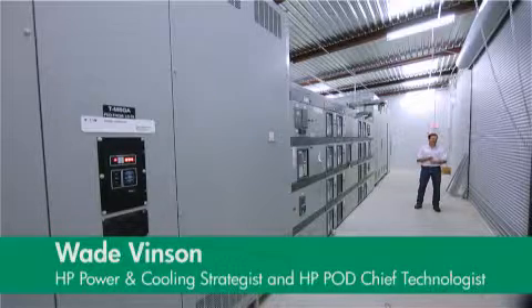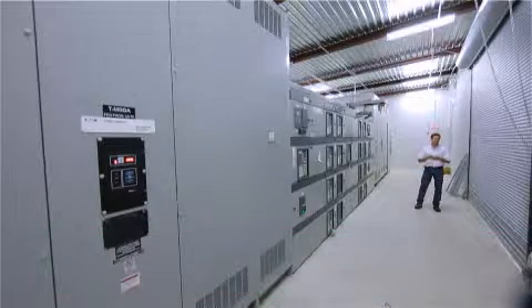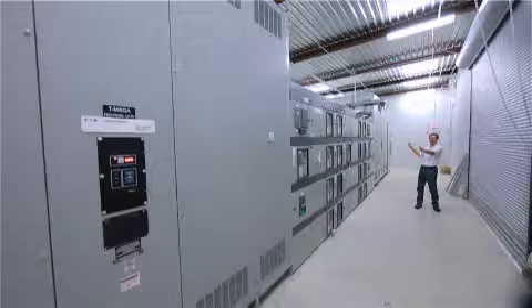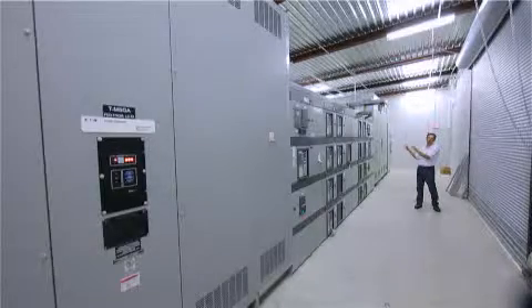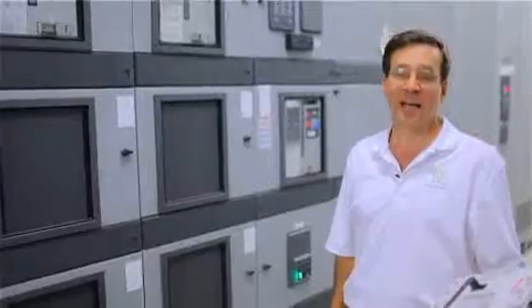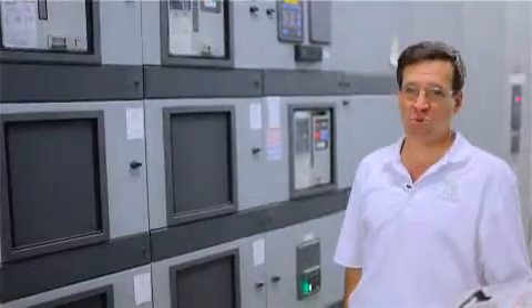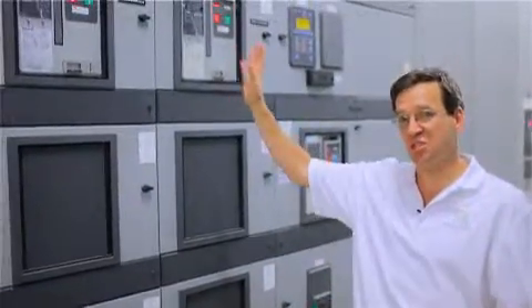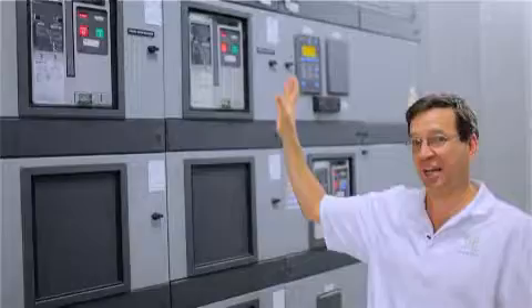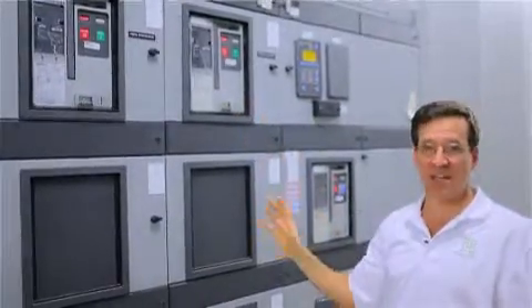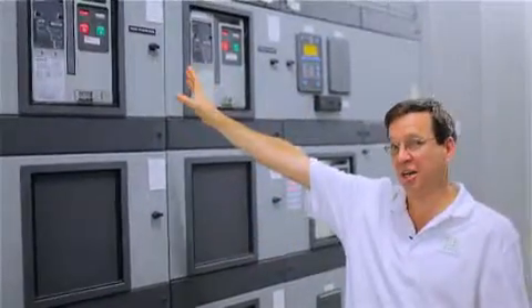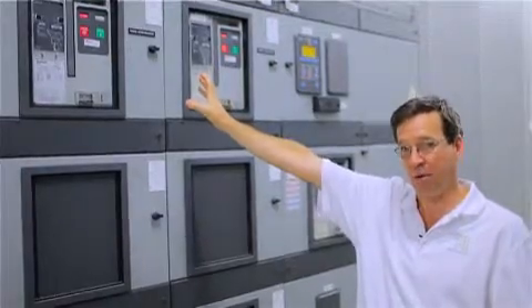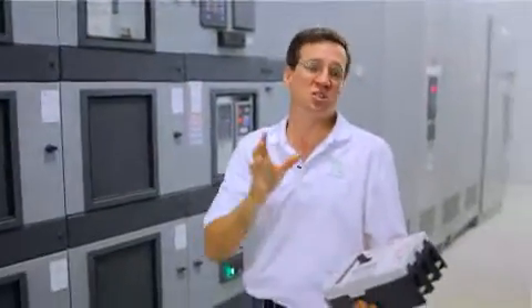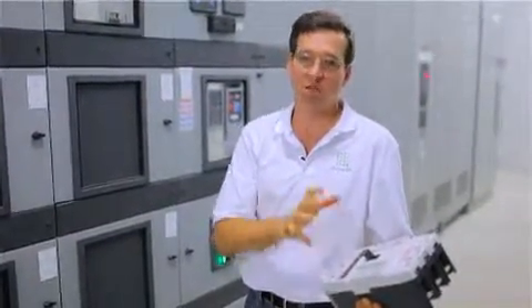Because every data center in the world, from 1 megawatts, 3 megawatts or more, is a collection of one or more 4,000 amp backplanes. As we've been developing pods over the last 3 years, we've been right-sizing to these commodity 4,000 amp backplanes. And that optimization continues down to the 1,600 amp breakers that come off of them, all the way down to the 200 amp breakers that feeds the rows of IT.